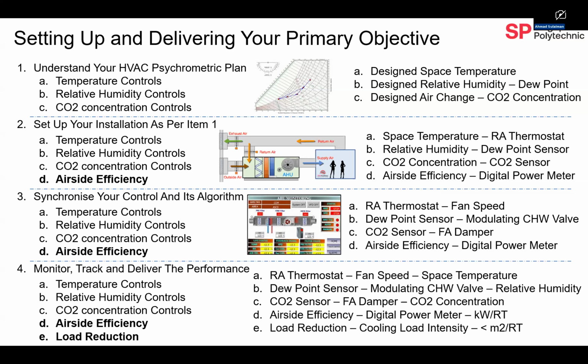This control will be used by your facility or operation guy to operate the AHU or PAU. If you don't have the control, how do you want to operate it? Most of the controls I saw on the air side have no humidity control. Everybody assumes it's going to be there, and that's the issue. So when you don't have control, you can't address your humidity issue, but you expect the technician on the ground to do it.